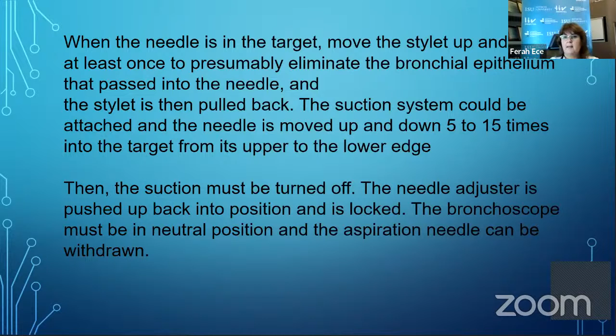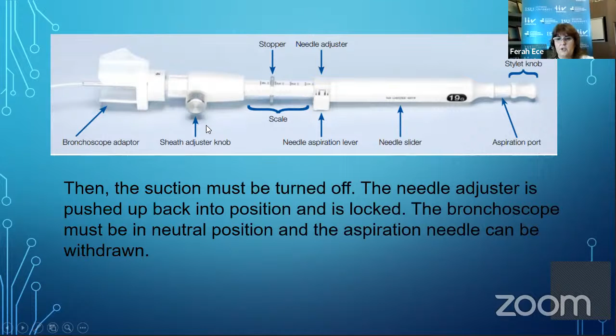Then the suction must be turned off, and the needle adjuster is pushed back into position and locked by pulling the lever. The bronchoscope must again be in neutral position and the aspiration needle can be withdrawn right now. So I'd like to repeat it with pictures again so you can understand and imagine it in your mind. First, we put the EBUS needle into the bronchoscope and we have to be sure that the scope is in neutral position in order to prevent bronchoscope damage.